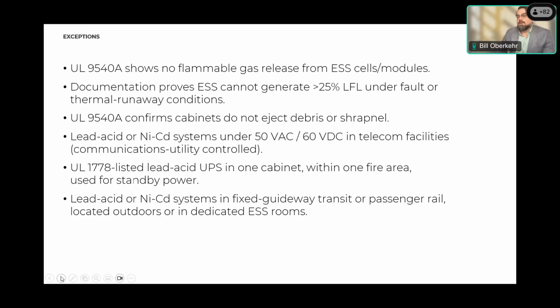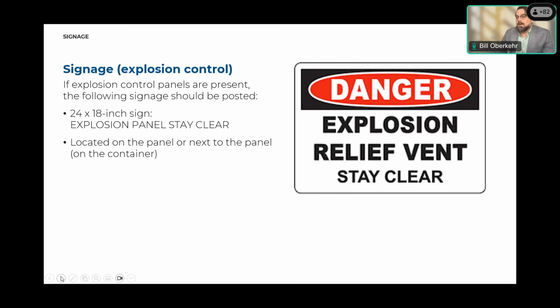This is the warning sign that I was talking about under the signage section. If you have those deflagration vents that are going to pop up to vent out explosive gases if there is a critical mass buildup of the explosive gas in the container, we need to have signage that shows where that deflagration vent will land should it pop off the system entirely, because again, that is a life safety hazard to first responders in the event of an emergency. Next slide, please.